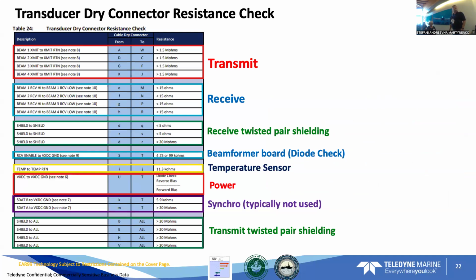And this kind of expands on that. Whenever you're actually doing a resistance check, this top portion will be your transmit twisted pairs, and you have the 4 measurements. Then you have the receive portion. You have the receive twisted pair shielding. You have the beamformer, which is actually your diode check also. The temperature sensor, power. This portion here is not really used anymore. I don't really know if anybody will see that in the field. And you have your grounding here, which is your twisted pair shielding.